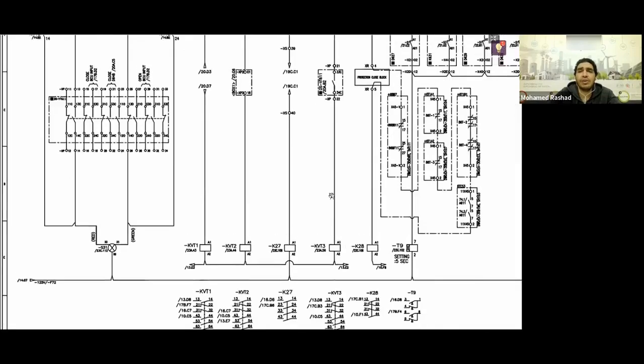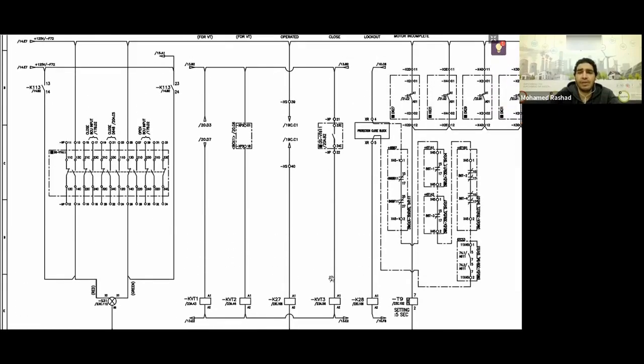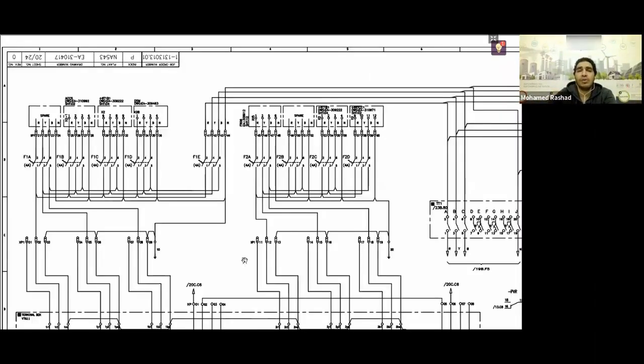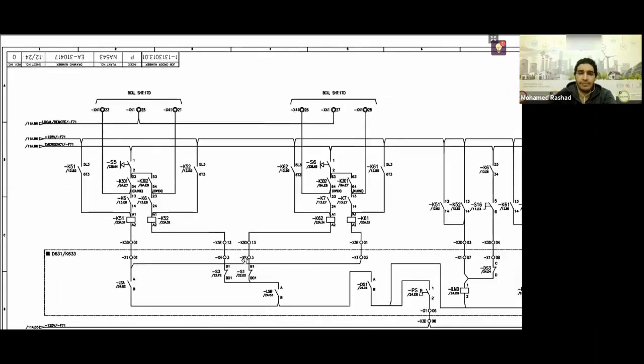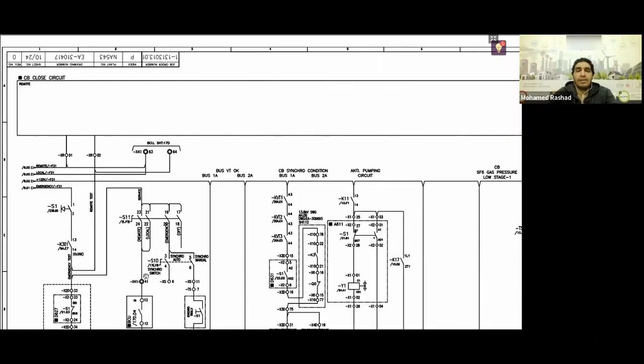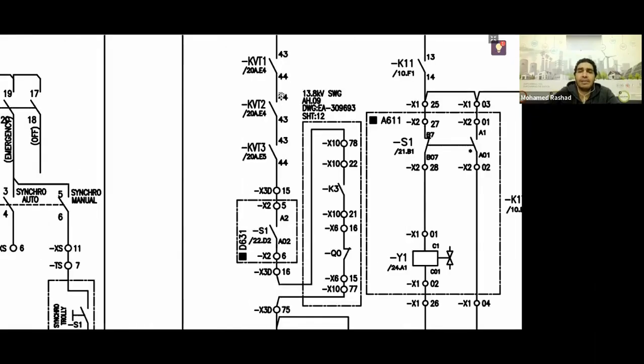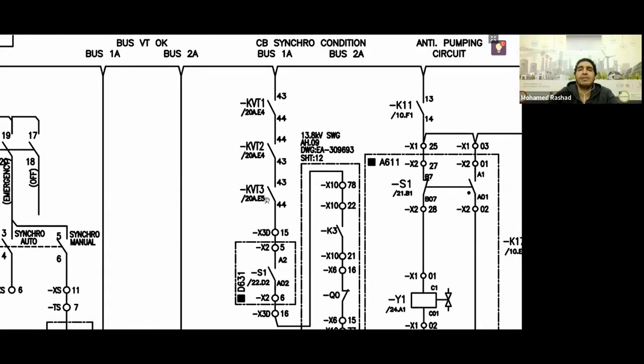When this contact closes, what does it do? It takes the positive from above and connects it to KVT3. So now I've activated KVT3, KVT1, and KVT2. One of them was activated when the VT isolator closed, and the other was activated when all the contacts present in the VT box in the GIS closed. Another one is activated when all the contacts present in my LCC panel are also closed. Okay, great. So now relays 1, 2, and 3 are closed.